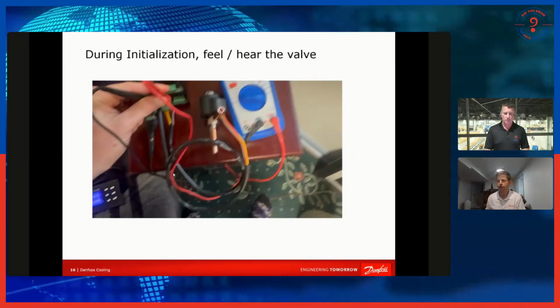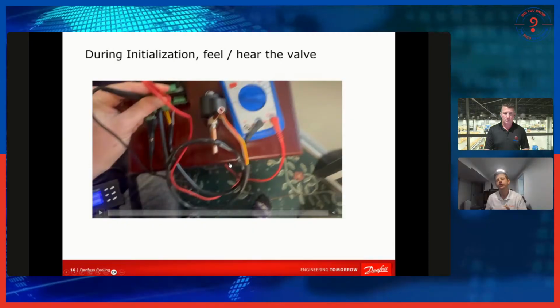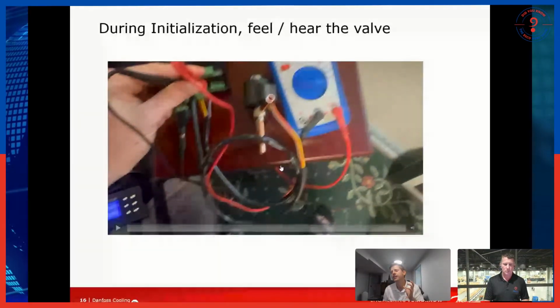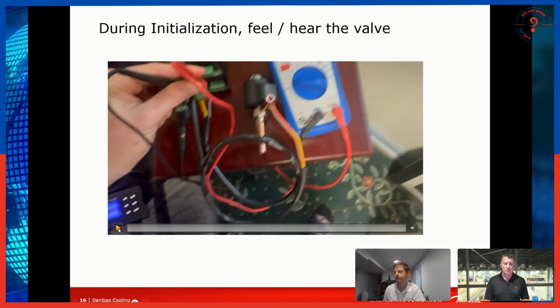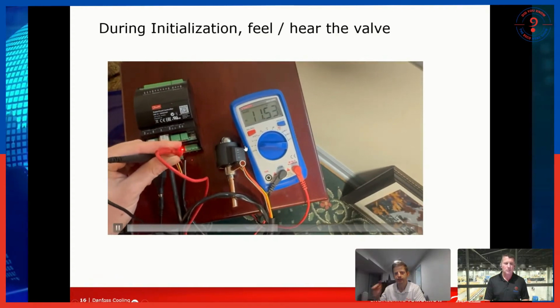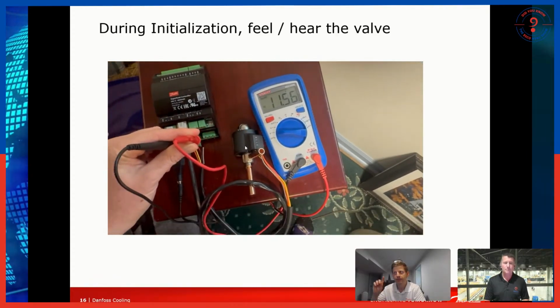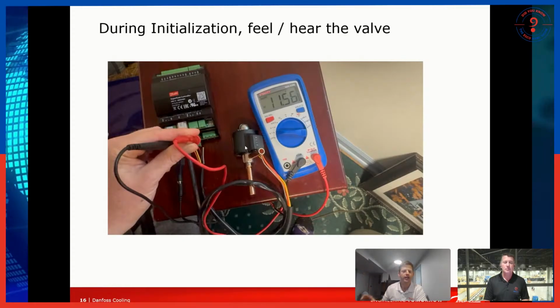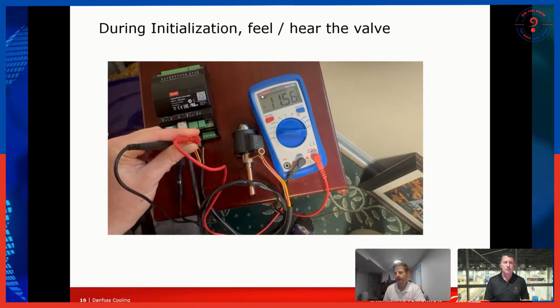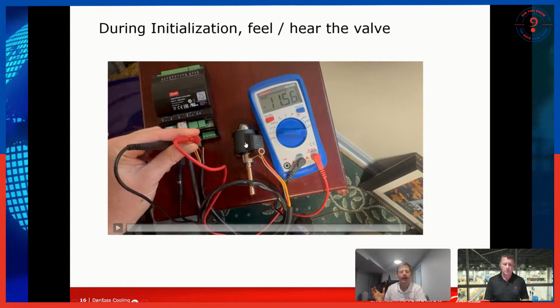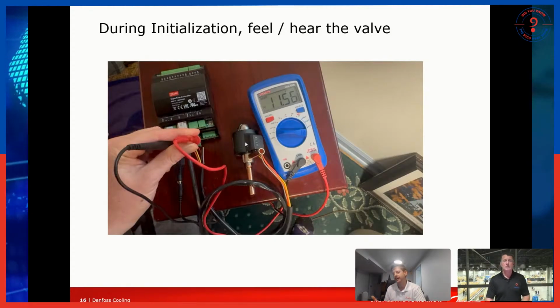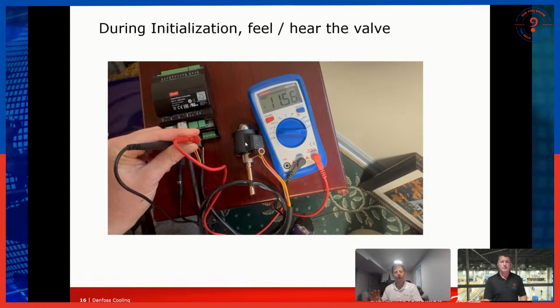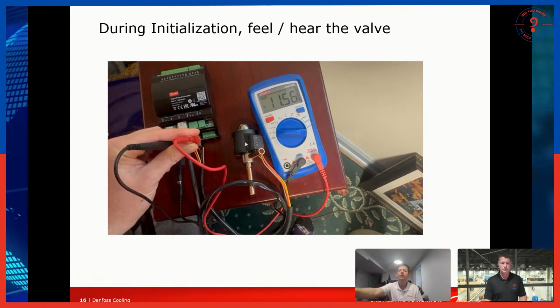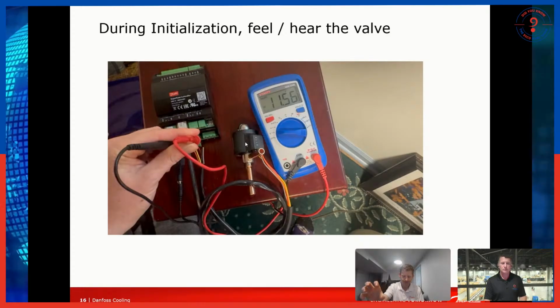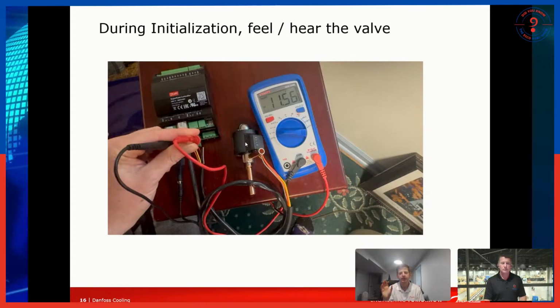And another thing you can do too, if it's all wired up, is when that control board starts up, you can usually hear or feel an EXV. So this, that tapping sound you were hearing there, that's the EXV making a sound and banging against this little table. And oftentimes it's not that loud. So if there's a compressor running, you're in a machine room or something like that, it might be hard to hear. But if you hold on to that valve, you oftentimes can feel it.